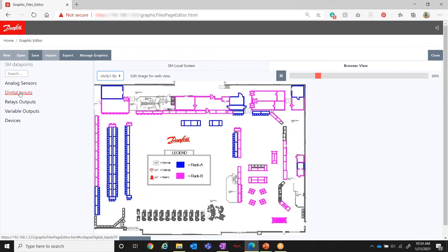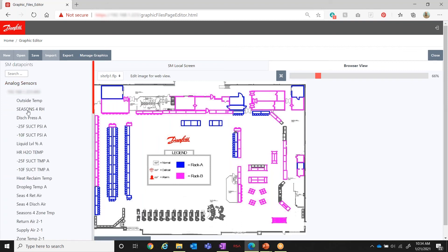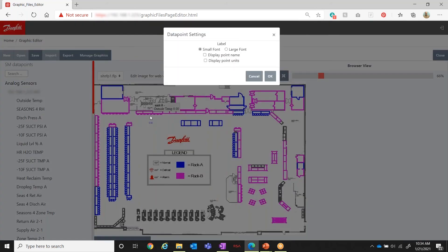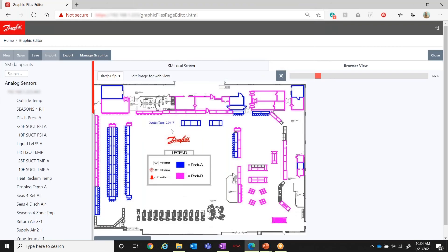Going back to the first drawing, we'll now overlay some data points. I open the data points panel and start with outside temperature — I drag and drop it onto the drawing. This is a temperature read. If I double-click on it, I can select a larger font, add the point name, and add units. Notice when I click OK it now gives a lot more information. If you don't have room on your drawing you may need to stay with just the data read. Once I change the settings, all subsequent data points I add will follow the same format.